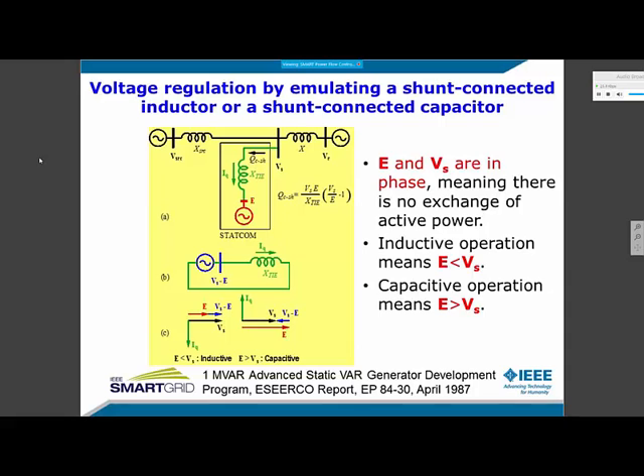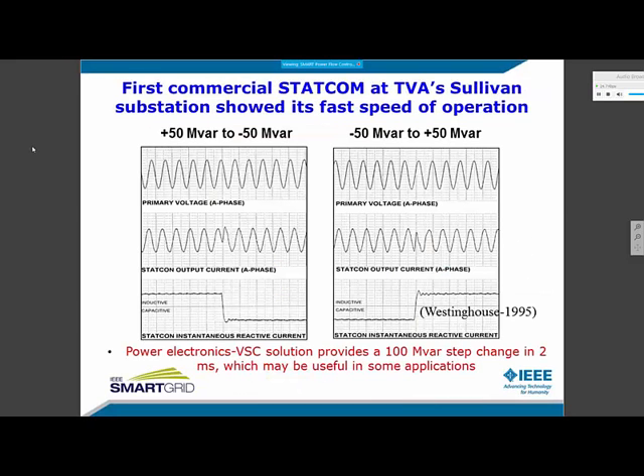Now this concept was taken to the next level by replacing this back EMF by an inverter, and that inverter was 1 MVA rated. It was demonstrated in the 1980s, and this reference gives you more about that project. Here is a result from the first commercial STATCOM application commissioned at TVA's Sullivan substation in 1995. Since the inverter has no inertia, the response time for a 100 MVAR step change can be in milliseconds, about 2 milliseconds, going capacitive to inductive or inductive to capacitive with apparently no transients.